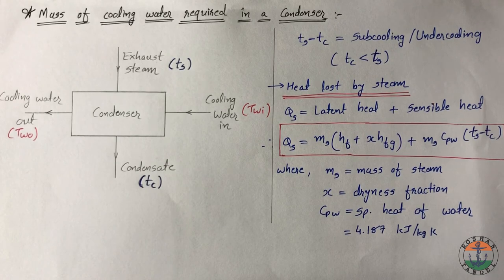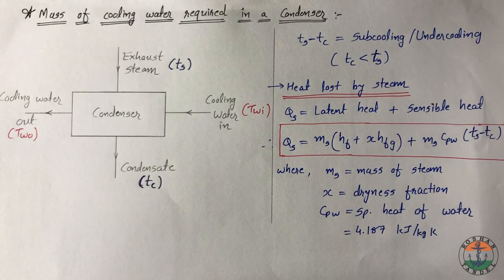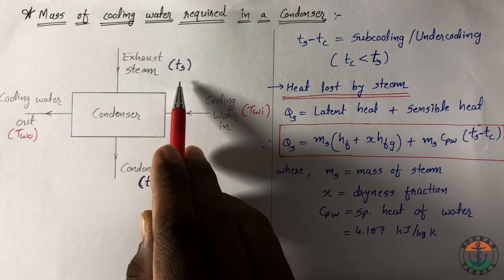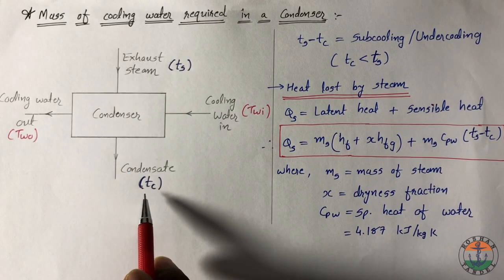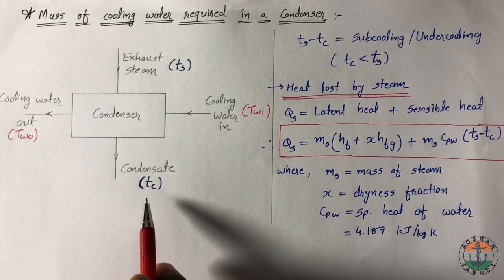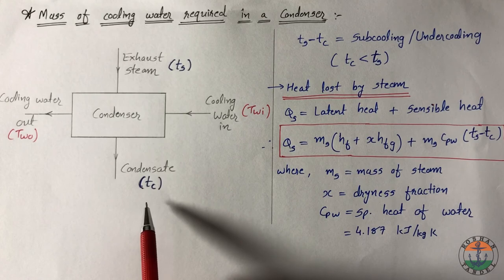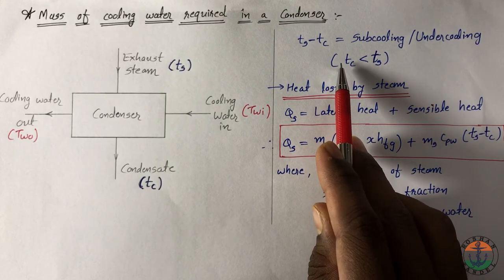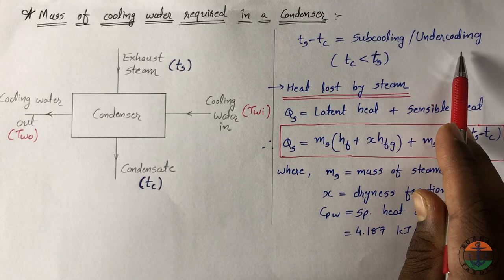Now how to calculate mass of cooling water required in the condenser. During condensation process, exhaust steam releases its latent heat at constant temperature and pressure to the cooling water. Ts is the saturation temperature of exhaust steam. But sometimes condensate is subcooled. After subcooling, suppose temperature of condensate is Tc. In this case, Ts minus Tc is called subcooling or undercooling.